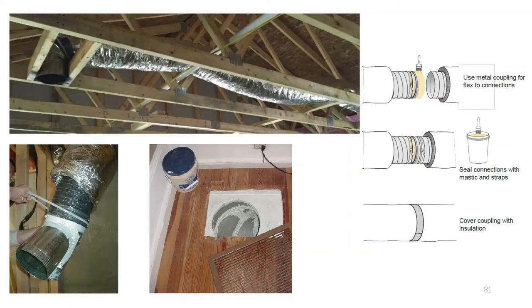Flex duct is easy to install and therefore very easy to install incorrectly. Our energy consultants have seen hundreds of ways that this has been done poorly. The inner liner must be pulled taut to remove airflow disturbing crinkles. Frequent supports are needed to prevent sags and cannot be too tight or they create crimps. The top picture shows both a sag and a slight crimp.